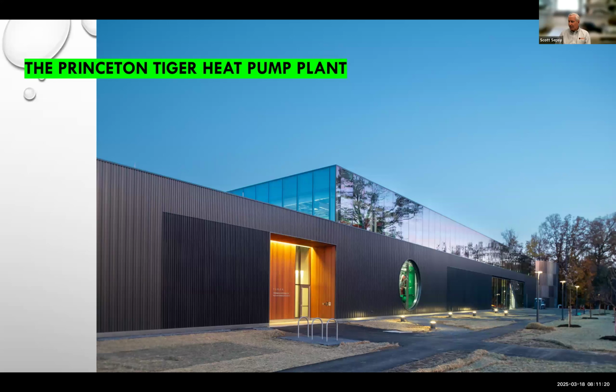This is the new Tiger heat pump plant as it's finished. It has two York heat pumps that produce 1,700 tons of cooling each and 28 million BTUs per hour of heating. This system has 1 million gallon hot and chilled water storage tanks, which you can catch a glimpse of at the back of the slide here.